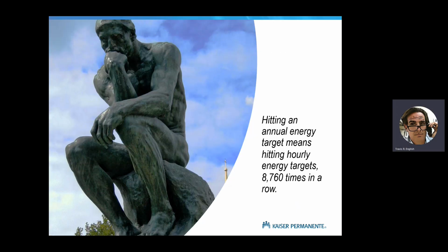So the overriding idea that we've come to here is that if you're going to hit an annual energy target, that means you need to hit your hourly energy targets about 8,760 hours in a row. So we might show our calculations to USGBC or the Energy Commission or the owner in units of per year. But what we need to do on the ground during commissioning and during startup is to validate those performance metrics in units of per hour. So the hour is the all important unit when it comes to validating our systems.